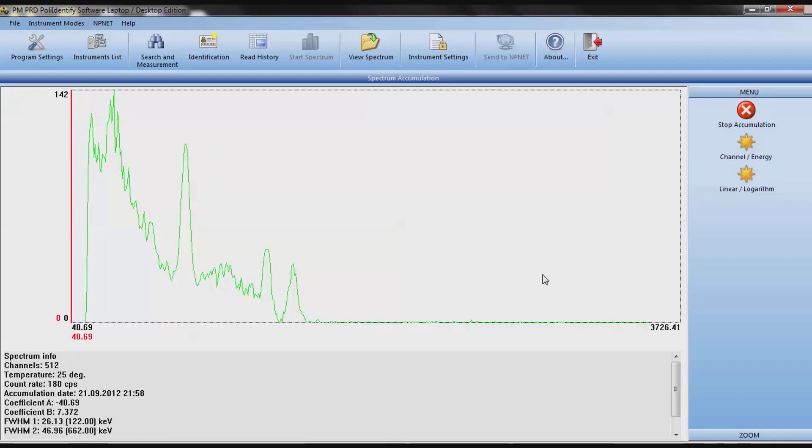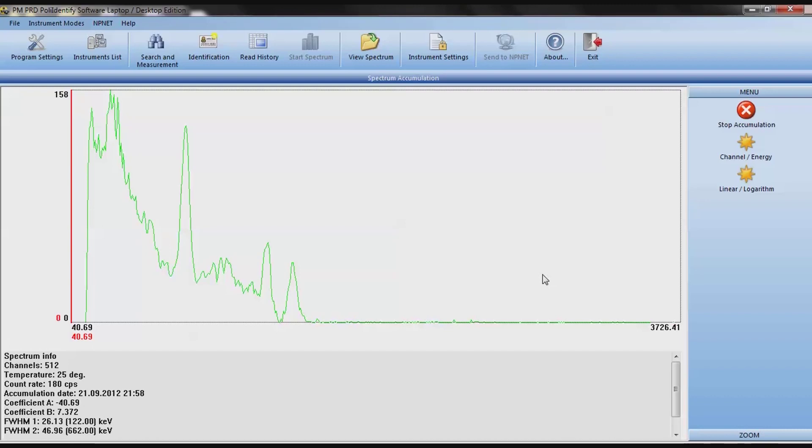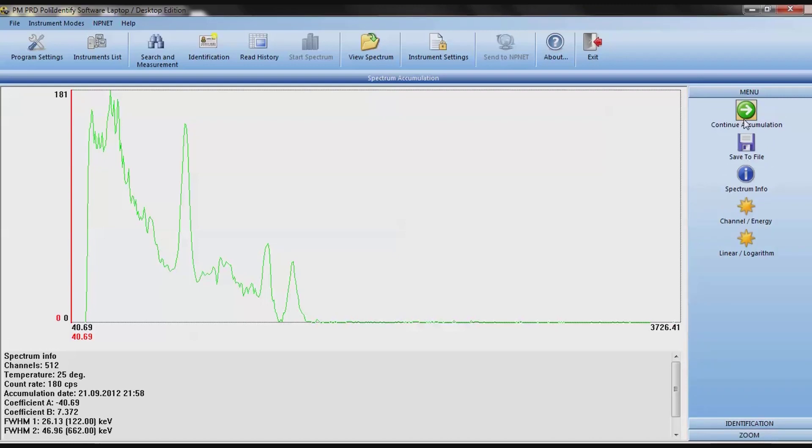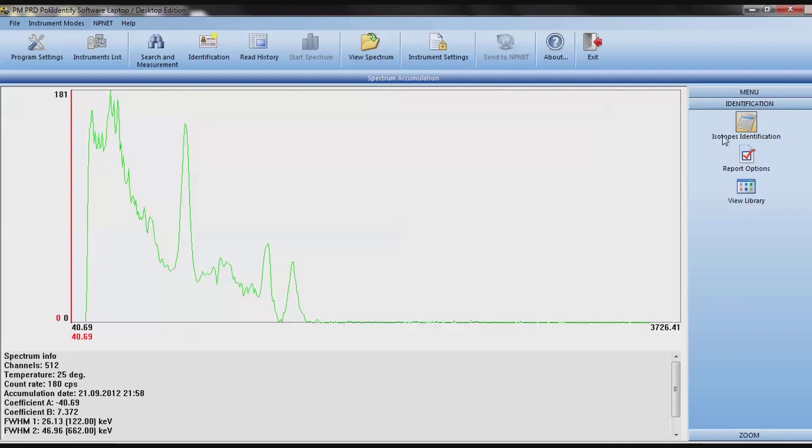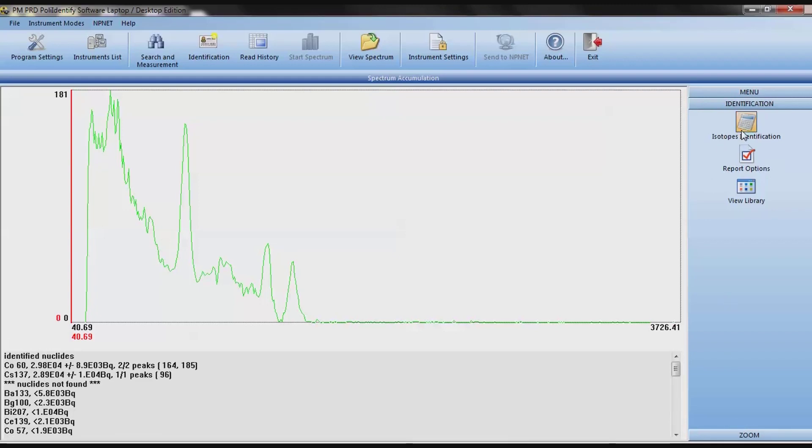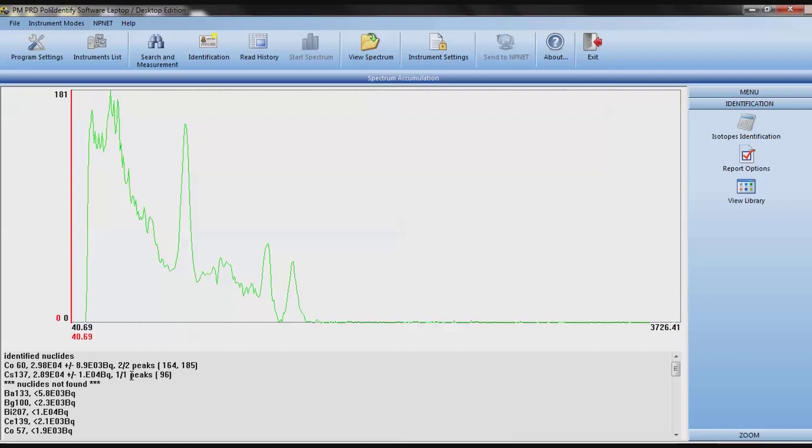This spectrum is getting pretty good now. We can stop it in a second and actually run an isotope identify on it and see what it comes up with. The amount of activity that's in the box. Now the reality is to do an activity analysis, we'd want to run this for a lot longer than we're doing here, because we're basically just about done. So we'll stop this. We'll run an identification, and this should match up with what we saw earlier. Now notice, it shows you what we found: cobalt-60, cesium-137. And it also shows a list of what wasn't found. And if you were to scroll down, it's quite a long and extensive list. So you know what isn't in it, which is kind of interesting. Now these readings are quite low compared to what's actually in here. If you gave this more time, it would have actually come up with more accurate readings in activity. But, you know, that's fine. So we should probably open up the box now and see what's inside of it. Gamma spectroscopy truly is fun.